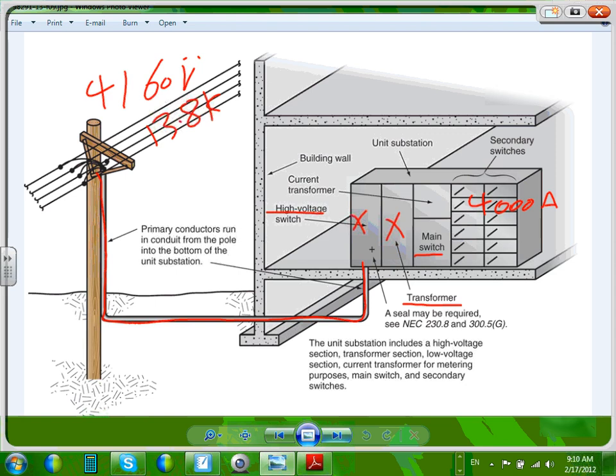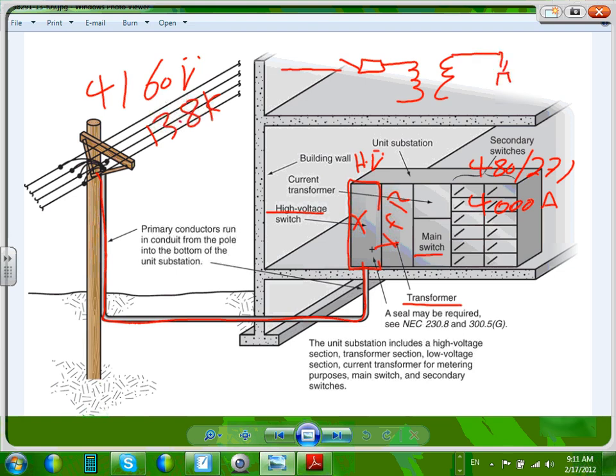So up to this point here, all this is high voltage. What high voltage? 4160. When you come over here, it becomes 480/277 because you went through a transformer inside. XFR, transformer to transformer. So in reality, it looks something like this when you draw a riser for it. You fuse it, then you come to a transformer. Out of the transformer, you go, in this case, fuse it, you put the fuse over here, and then you go to your panels. And these are also circuit breakers.